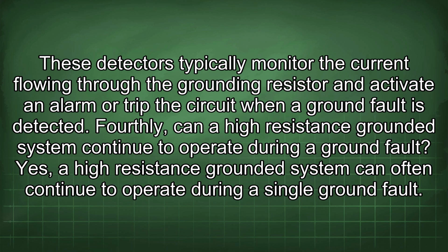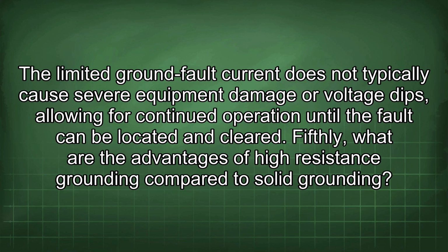Fourthly, can a high resistance grounded system continue to operate during a ground fault? Yes, a high resistance grounded system can often continue to operate during a single ground fault. The limited ground fault current does not typically cause severe equipment damage or voltage dips, allowing for continued operation until the fault can be located and cleared.